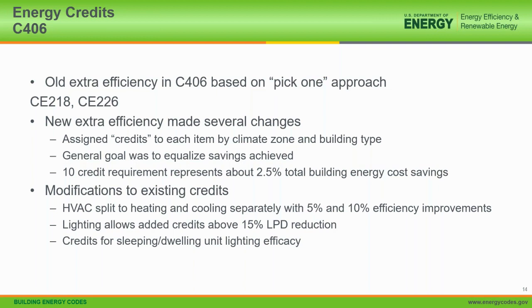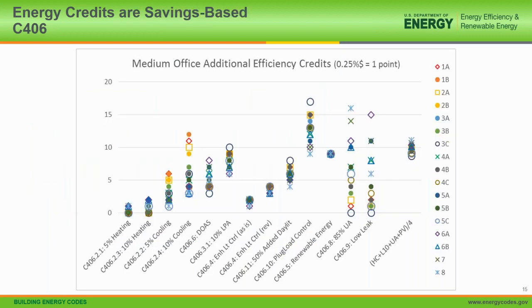Also, lighting allows credits above 15% lighting power reduction. Before, the old credit was just a 10% reduction. And there were also some credits added for sleeping and dwelling unit lighting efficacy, as those were pretty much left out. They don't have a lighting power density approach you have in most commercial spaces.